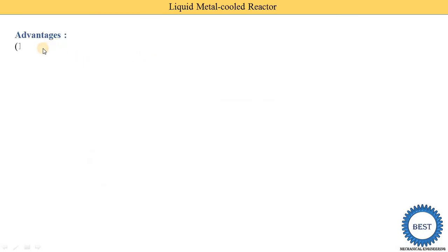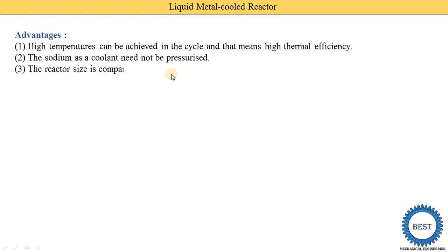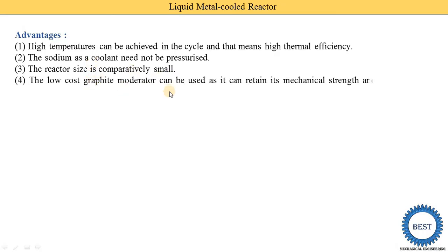The advantages of liquid metal cooled reactors are: first, high temperatures can be achieved, resulting in high thermal efficiency. Second, sodium as a coolant does not need to be pressurized. Third, the reactor size is comparatively small. Fourth, a low-cost graphite moderator can be used, as graphite retains its mechanical strength and purity at high temperatures.